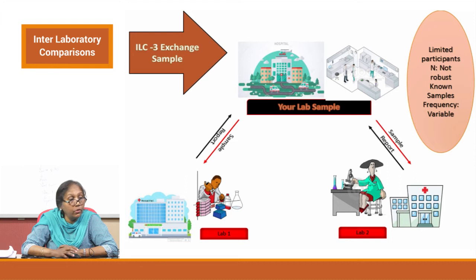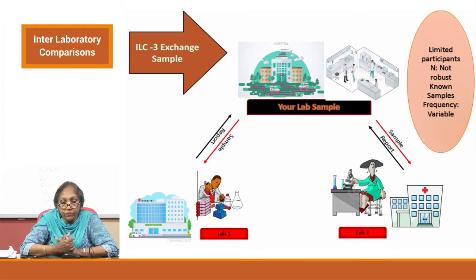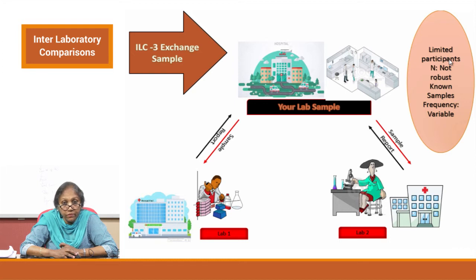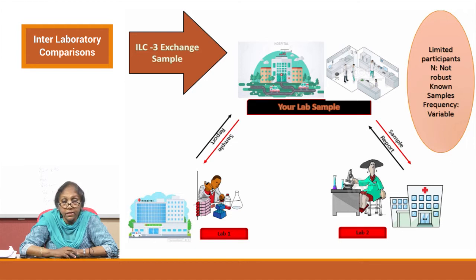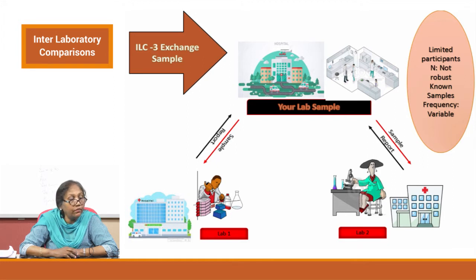The third option is exchange of samples. Your lab has a sample, you send it to other labs, and they send you a report so you can compare yourself with the group. The problem is that participation will be very limited — unless you have a certain number of participants, you do not get a robust statistic. If you have no other option and no EQAS programs are available in your area, you can consider exchange of samples.